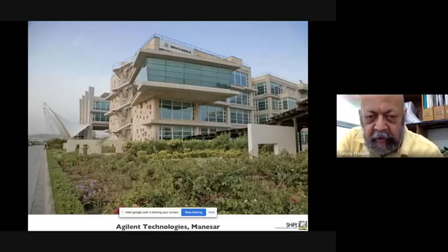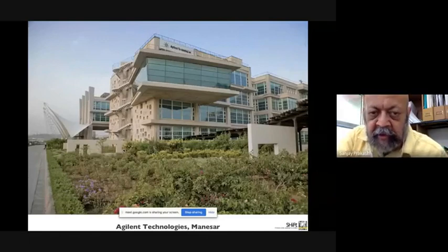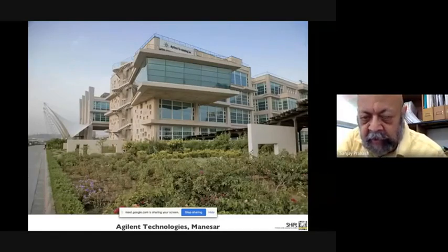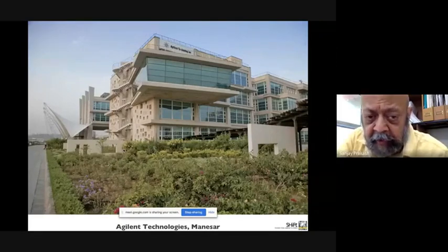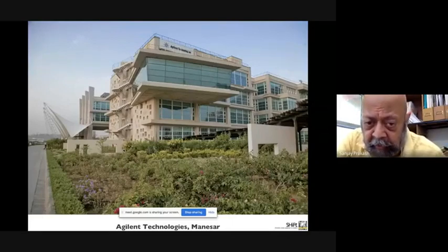I must also admit that we worked very early on, much earlier than is normally done, with our HVAC consultant, Mr. Gyan Modgill, who incidentally got an HVAC award for this building called the Emerson Cup, which is given by the HVAC industry for, hold your breath, instead of 200 square feet per ton, this building was designed with 600 square feet per ton. And would you believe that in the last 20 years that it's been in operation, or 16, 17 years, it has never had to use the full capacity. So it probably is using something like 800 square feet per ton.